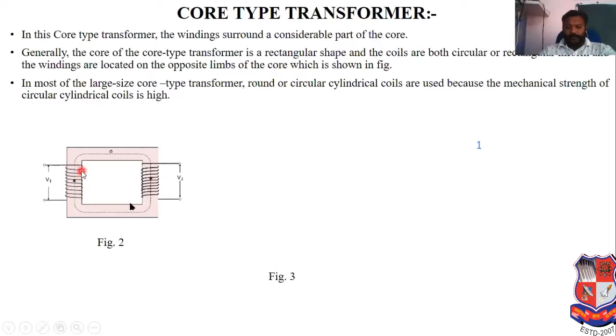So in this core type of transformer, the windings surround a considerable part of the core. Generally the core of a core type transformer is rectangular in shape, as you see, and the coils are both circular or rectangular in form. The windings are located on opposite limbs of the core, which is shown here. Sometimes LV is mounted on one limb and HV on the other, and here also an LV winding and an HV winding are there according to this construction. But the major difference in the core type is that the windings are mounted on two different limbs.